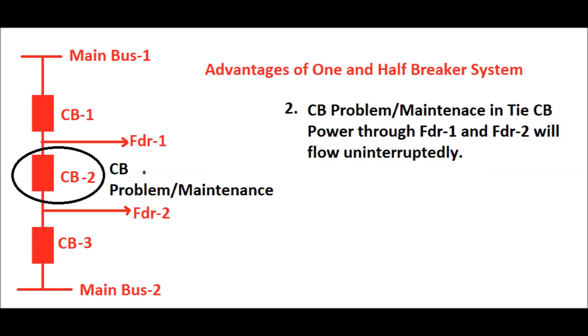Consider a problem in the tie circuit breaker CB2, or if CB2 needs maintenance. In this case also, feeder 1 and feeder 2 receive power uninterruptedly. Feeder 1 gets power through main bus 1 via CB1 in closed position, and feeder 2 gets power through main bus 2 via CB3 in closed position.